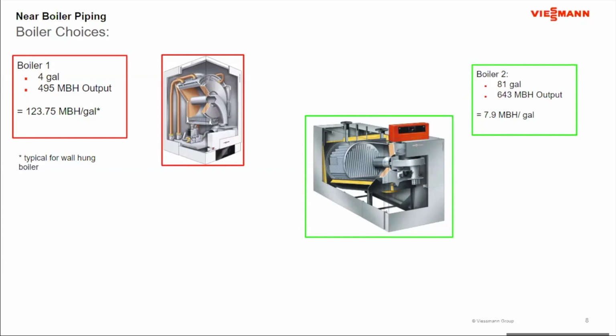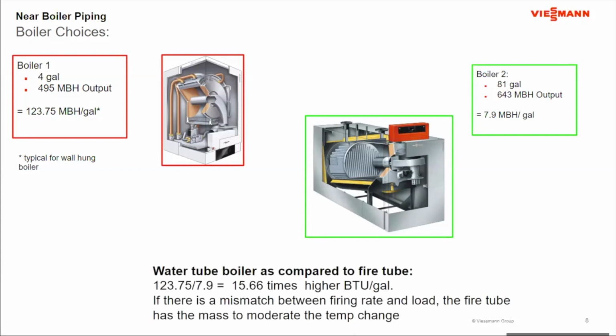So what does this really mean to me and why am I bringing this up? Now when we look at a comparison between the two, I divide the 124,000 by 8,000, and I get a ratio where this boiler here has about 15.5 times the output per gallon of water compared to this boiler here. Why is that significant? It's really significant when we have a mismatch between the firing rate of the boiler and the load of the system. Mainly, I'm firing the boiler at a higher firing rate than the load of the system, okay?